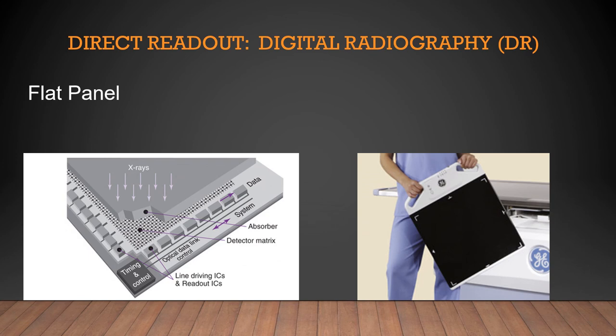So you have a flat panel that has a handle because it's very heavy. When an exposure is made, the sensing or storage component within the pixel contains the image information. The image is then read out line by line via the changing of the control line voltage, so each pixel is connected to its corresponding data line at the bottom of a column. Once the signal has been released, the energy is then transferred to the electronics that are attached to the edge of the array.